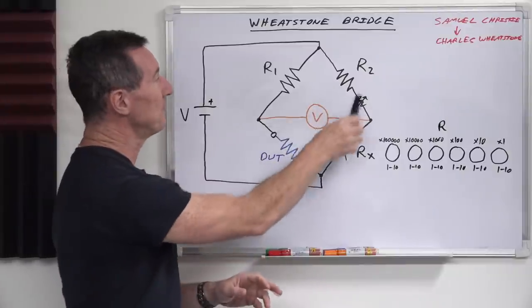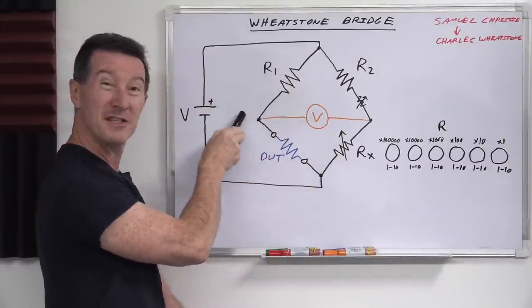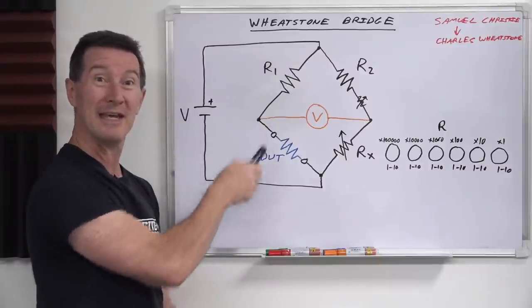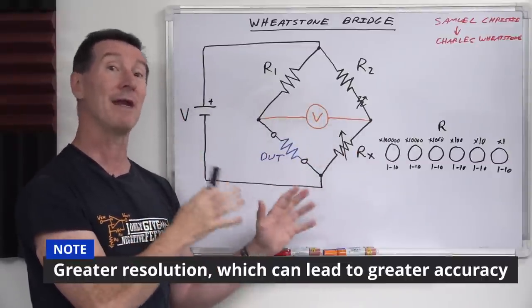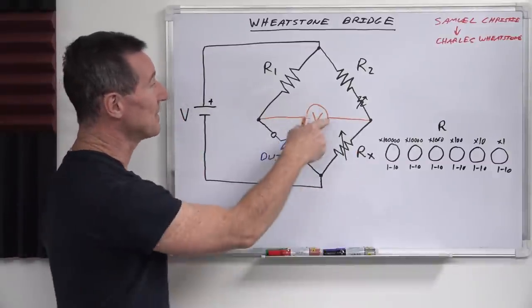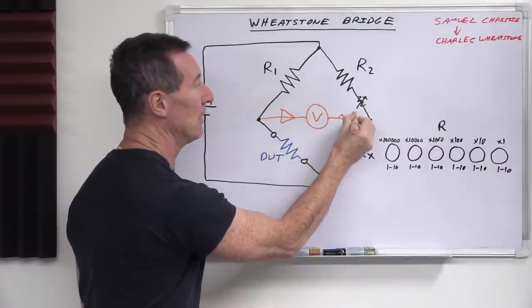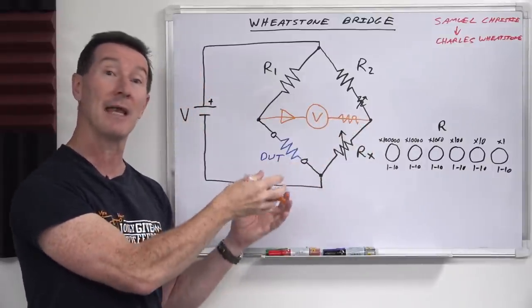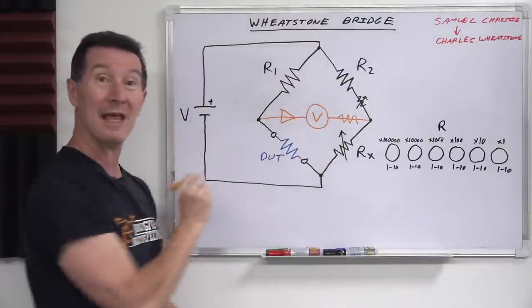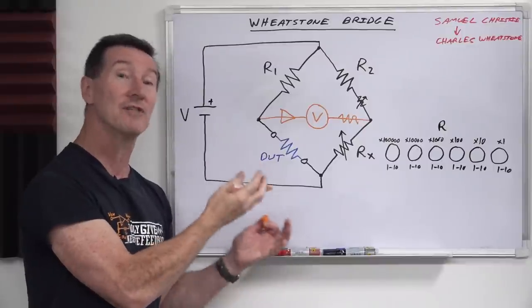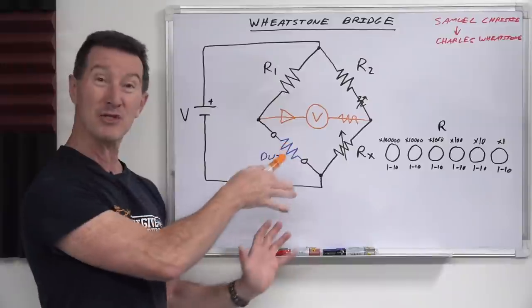And the great thing about the Wheatstone bridge is that you can measure incredibly accurate stuff. And the great thing about the bridge configuration, as opposed to just like a single voltage divider, you could do a voltage divider and just read off this node here relative to ground point here, and with a, you know, a precision voltmeter and stuff like that. But the bridge configuration allows you to get much greater accuracy. And as I said, in this particular case, this is actually an electrometer in here. So you'll have an amplifier like this, and you can have different range resistors also in here like this, and you can select, that was that sensitivity adjustment that we were playing around with. So we've basically got an amplifier with an electrometer in there, so you can even measure more precise values close down to zero volts.